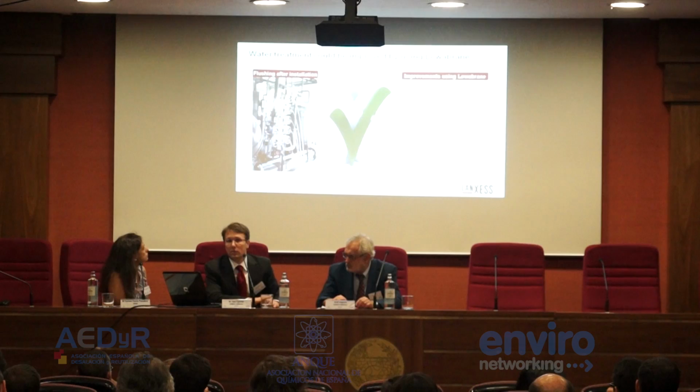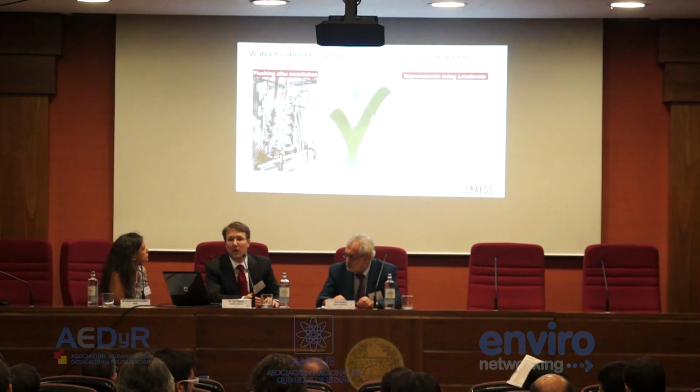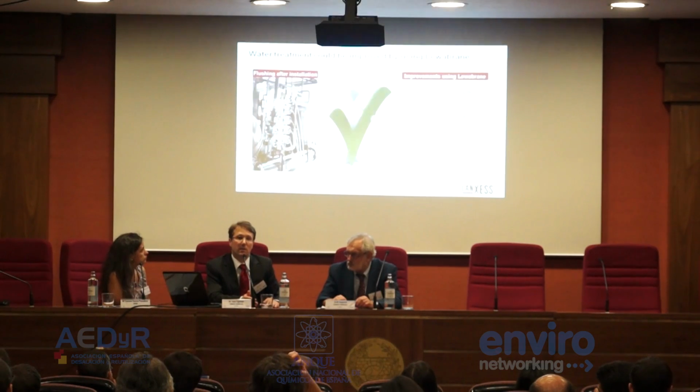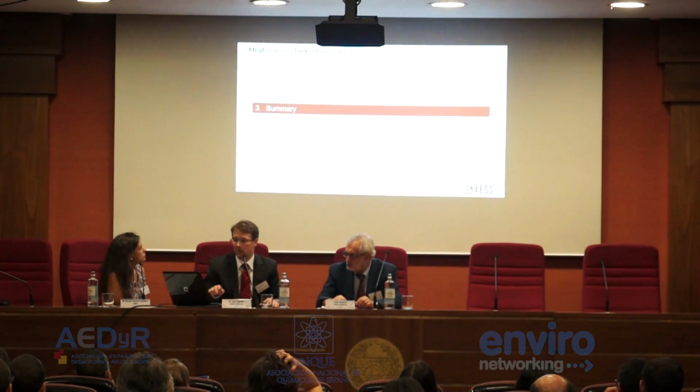So finally we could give them an energy saving of 40%, while simply moving from a low energy seawater membrane to a standard brackish water high rejection membrane. We could at least give them in this 1 year period a constant high rejection, and due to the higher rejection of the membrane, they could extend the life cycle of the ion exchange unit.